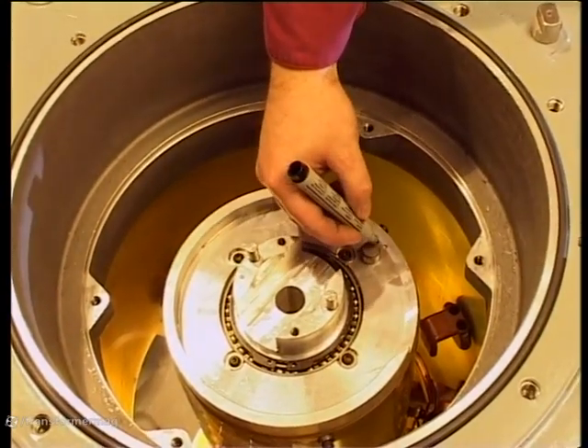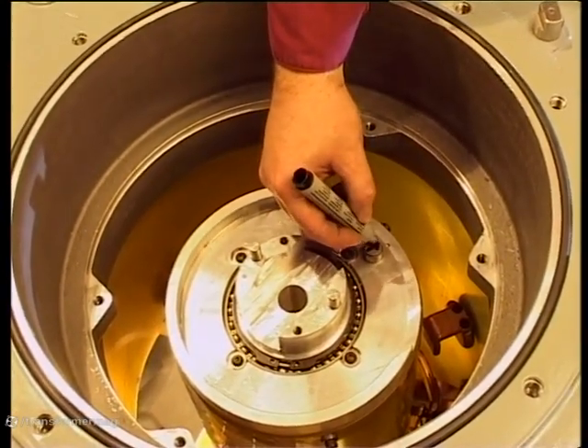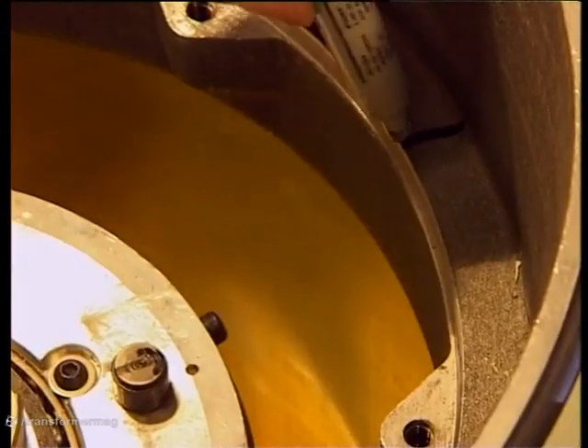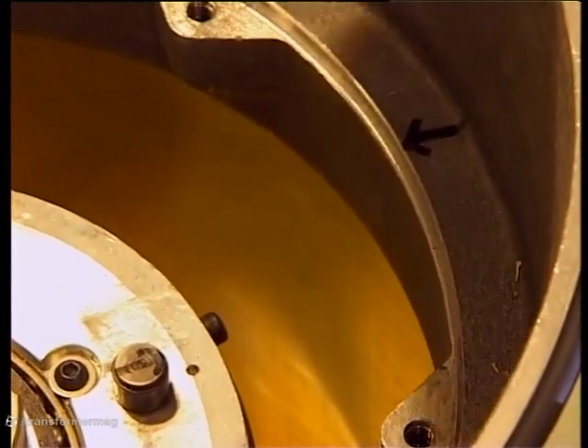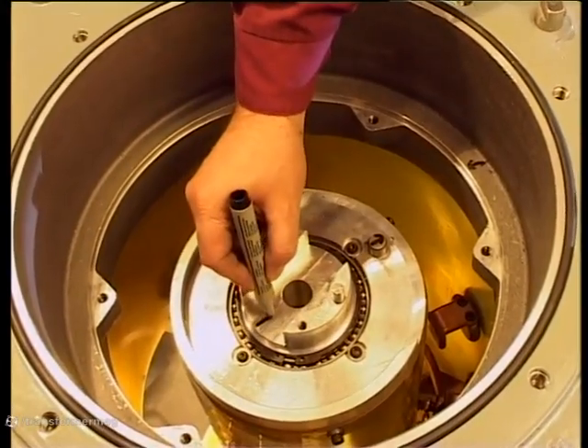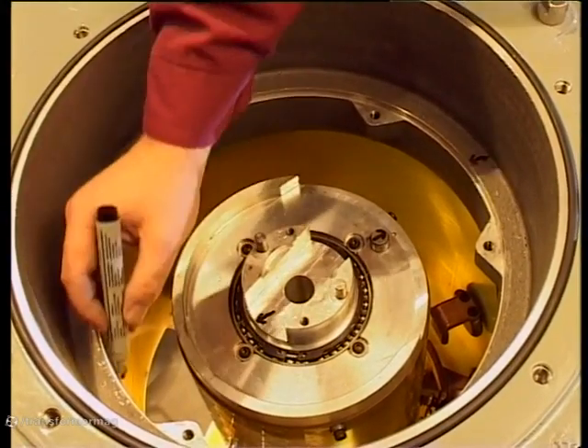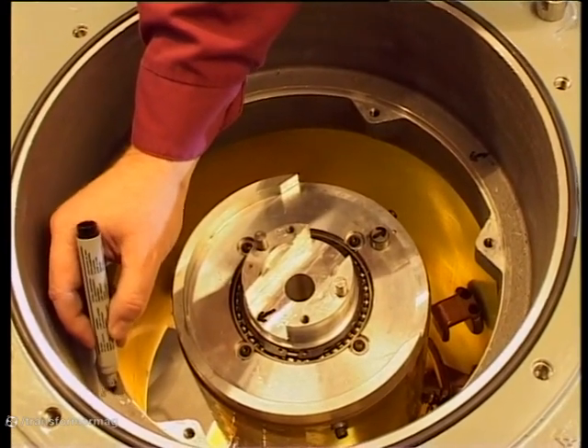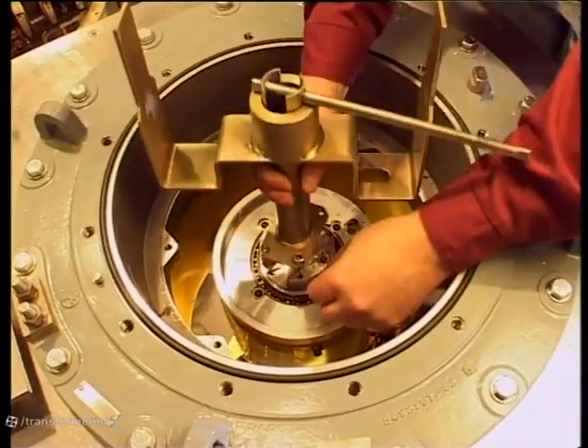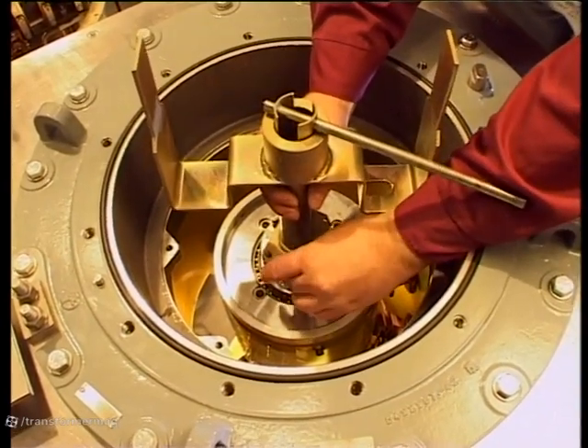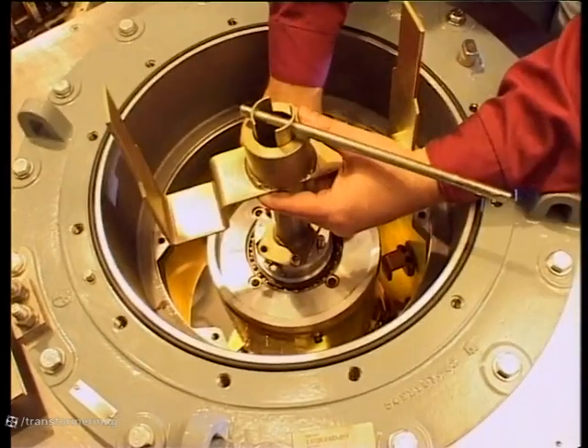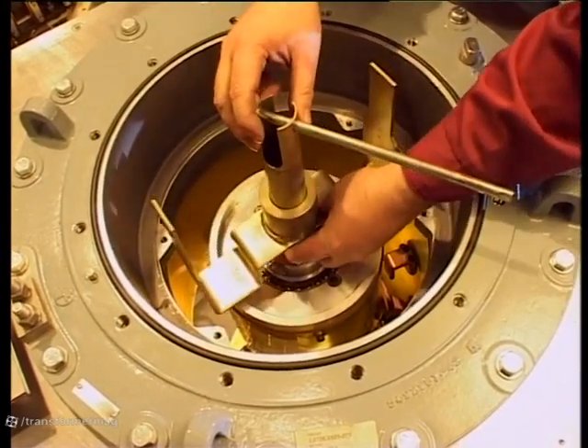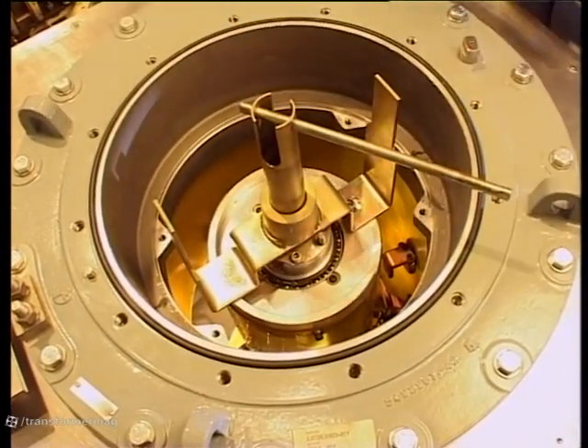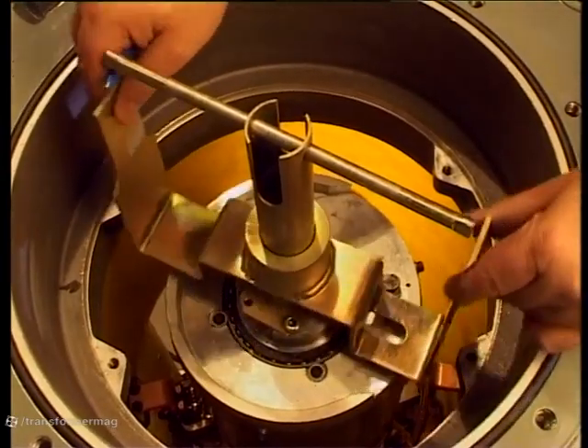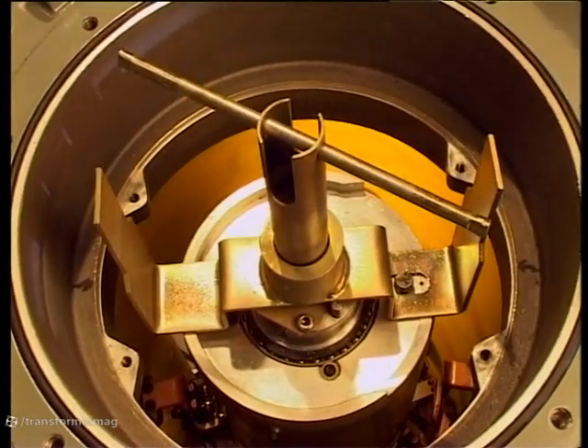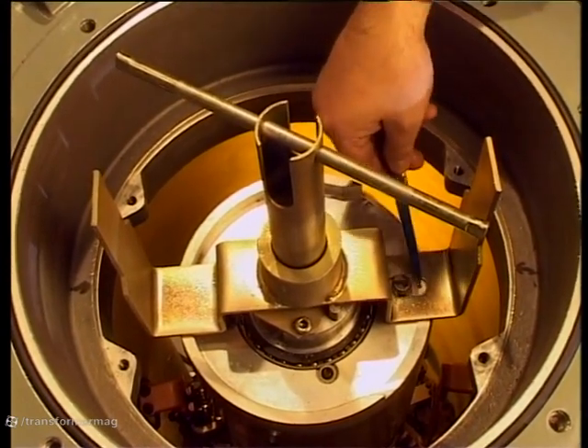Before lifting, mark the changeover selector drive roller and the position of the fine selector contacts against the outer edge so that you can refit them in the correct position. Attach the lifting and operating tool in the two M8 holes at the upper end of the selector switch. Grasp the outer arm of the tool and turn until the roller on the changeover selector enters the slot in the tool arm.